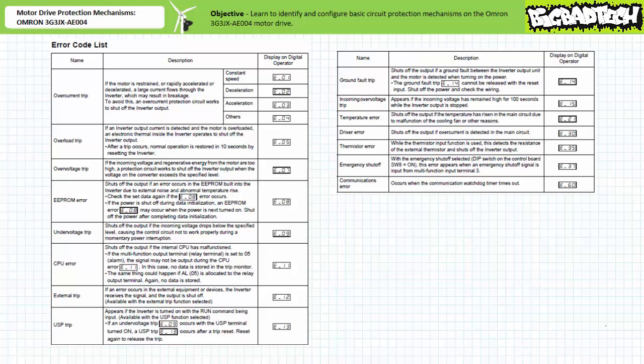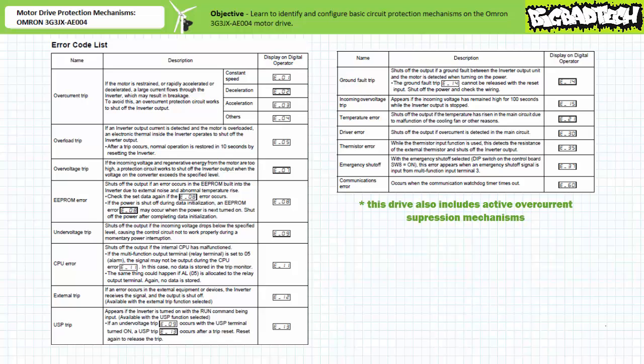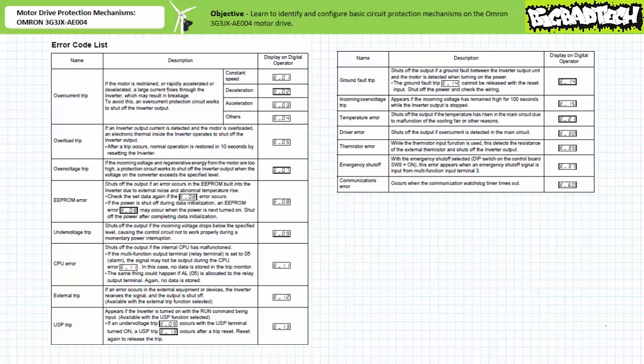Alternate responses to a fault condition include an immediate restart or a restart after a user-customizable wait time. Additionally, the restart experience can be customized to initiate with an acceleration period, match frequency, or match frequency then decelerate. Beyond this customized restart ability, the OMRON 3G3JX AE004 motor drive also includes the ability to ride out momentary loss of supply voltage for a brief time, potentially freeing an ongoing process from interruption.